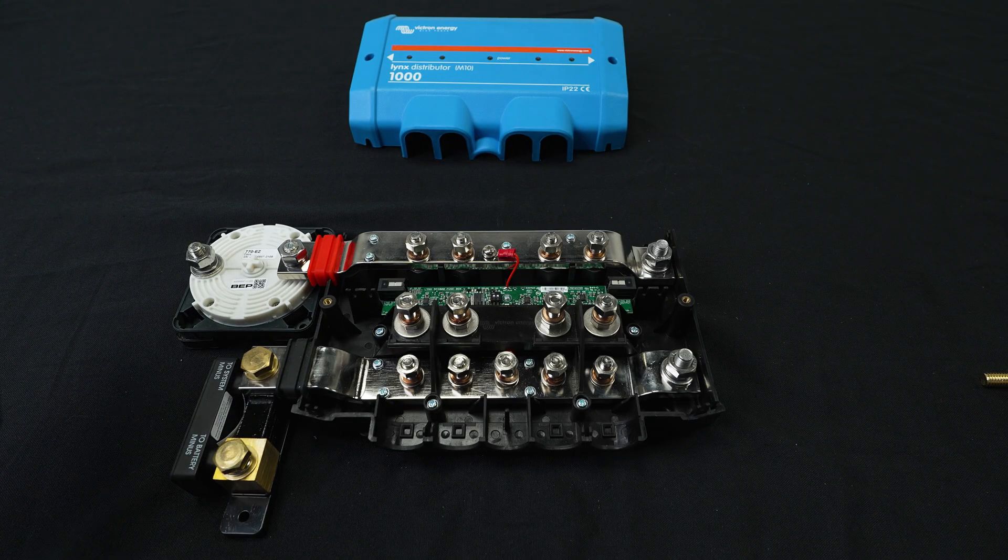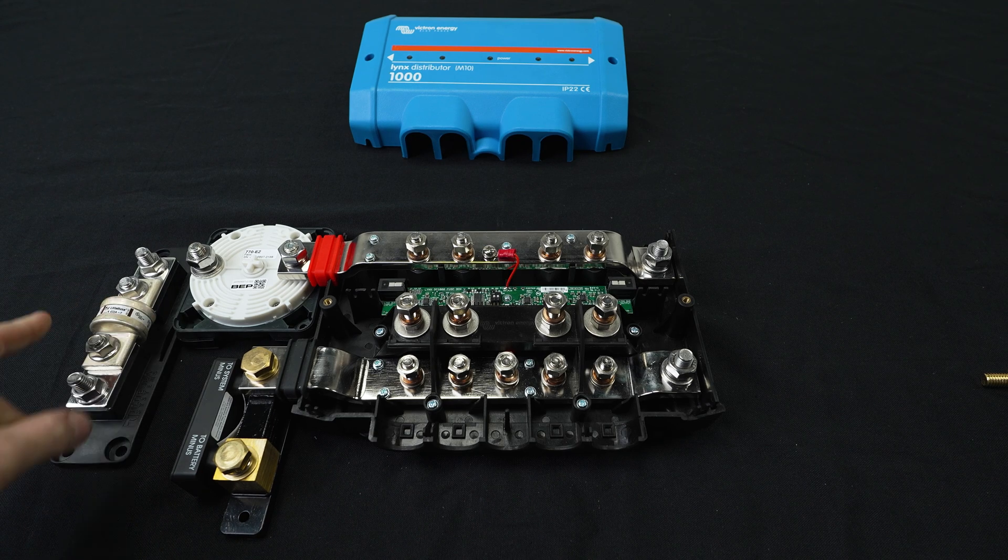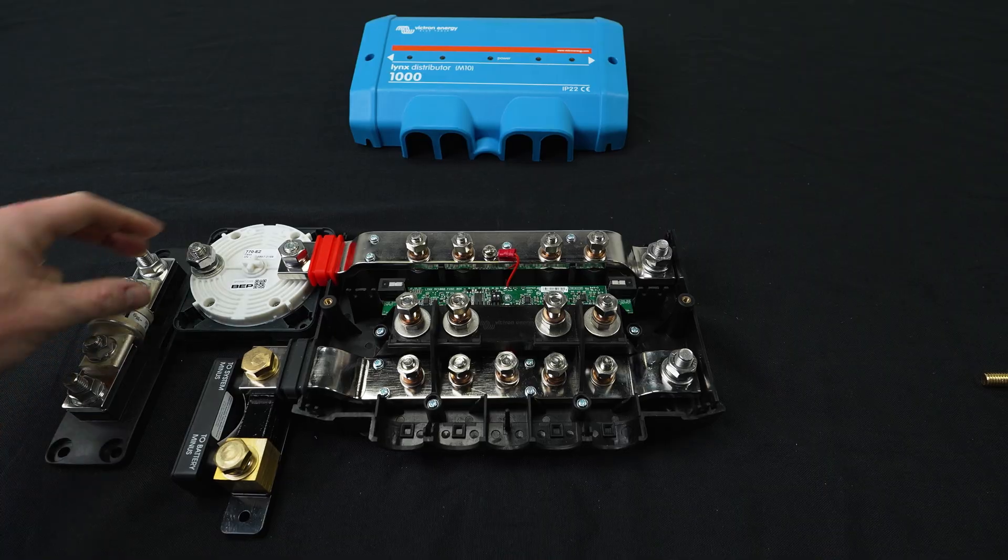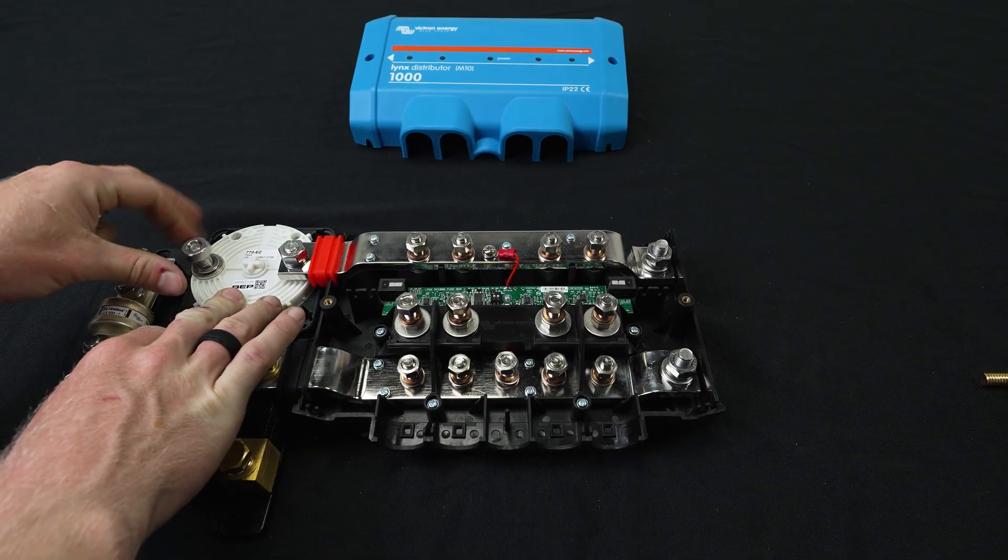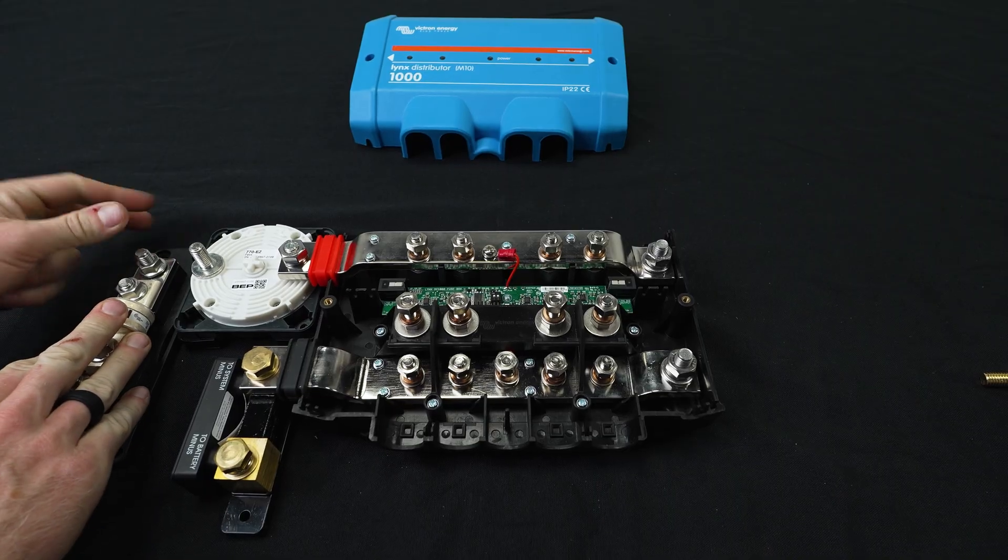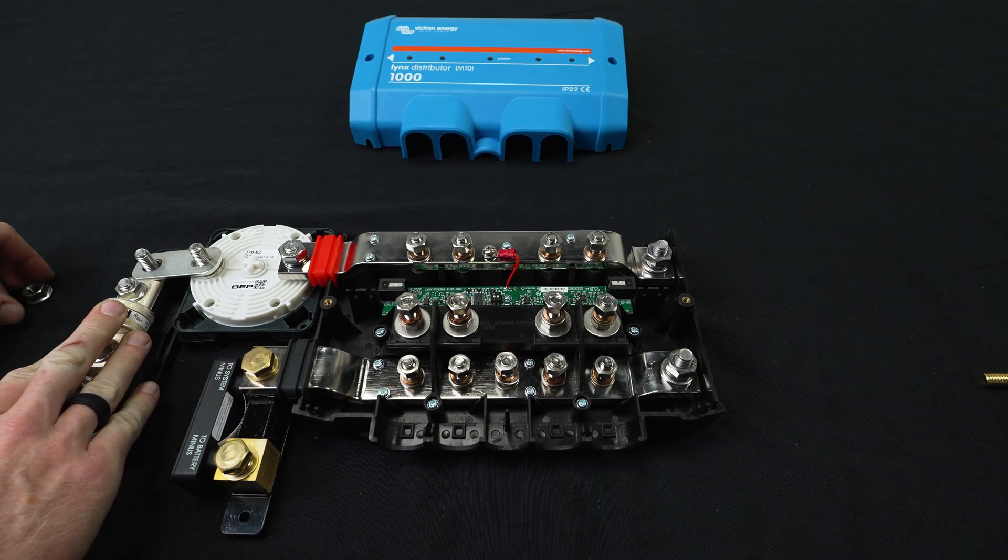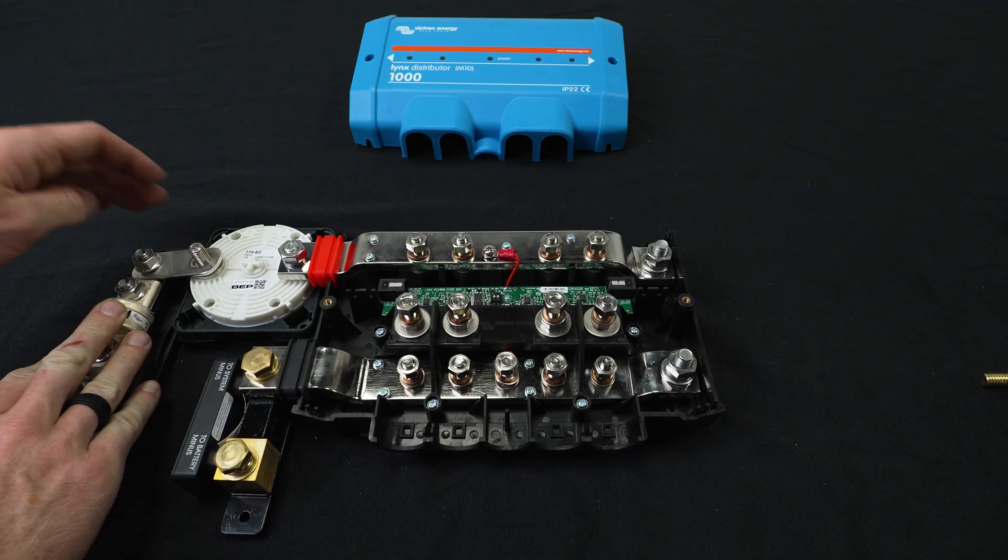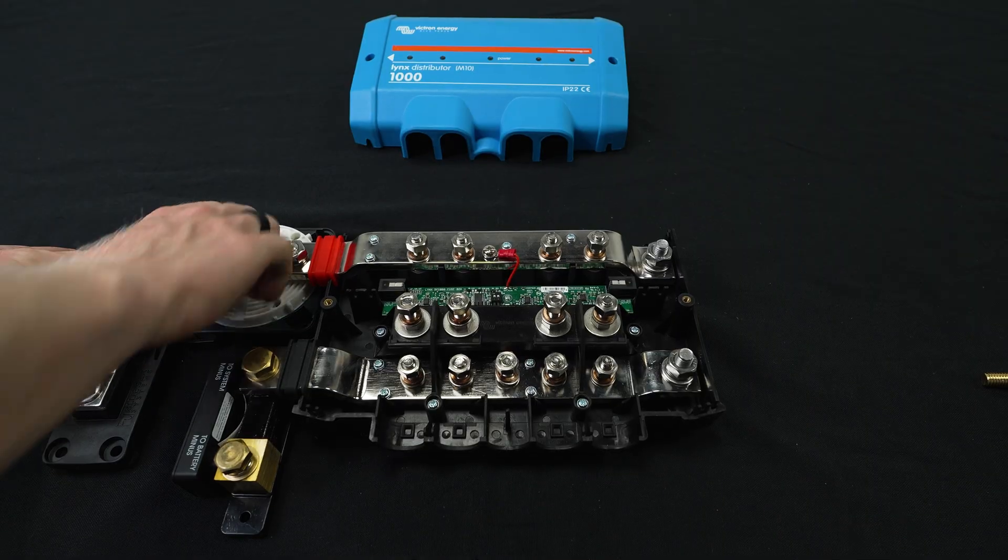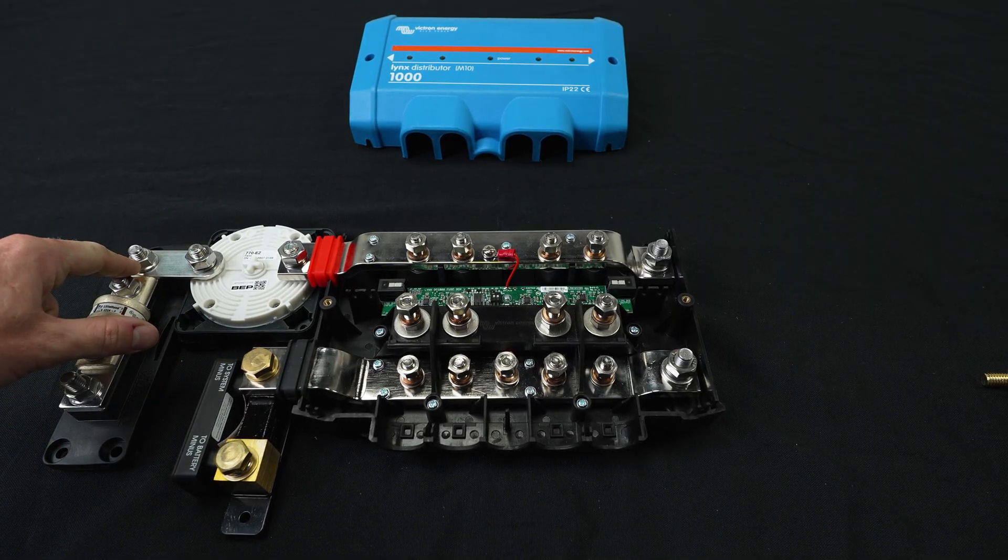Threads in there nicely. And this is asking for a 20 newton meter torque spec. Last but not least, if you're looking to install a class T fuse, you can position that to the left of the shunt. We sell a little spacer to go underneath. I don't have one handy right now, but we will link that in the description. And you'll use the link bar that we provide to link the two together. And again, the torque spec on this is 20 and this is going to be 20 as well.